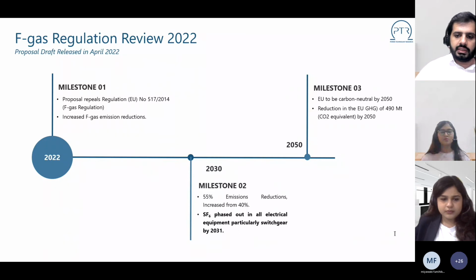For medium voltage switchgear with higher voltages, greater than 24 kV but less than 42 kV, the cutoff date is January 1st, 2030. For high voltage switchgear with voltages higher than 52 kV but less than 145 kV, the prohibition date has been suggested as January 2028. And lastly, for equipment with voltage exceeding 145 kV, the prohibition date has been suggested as January 2031. So this essentially means that SF6 is proposed to be phased out in all new electrical equipment by 2031.